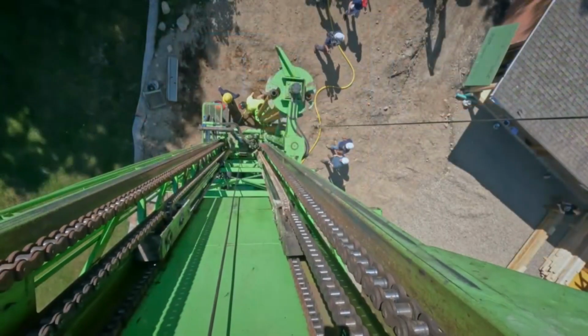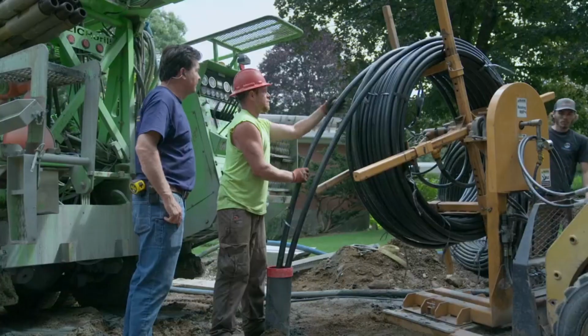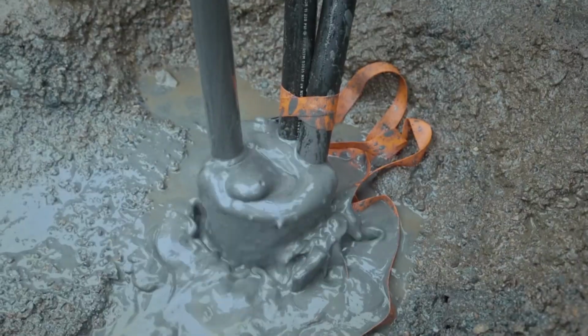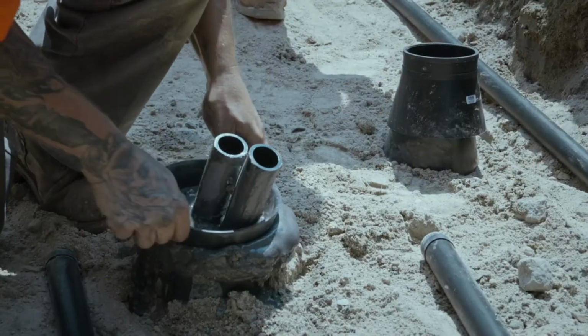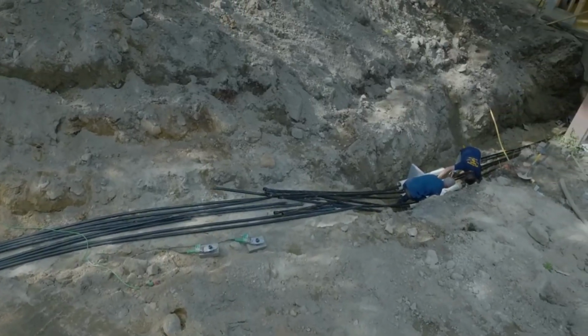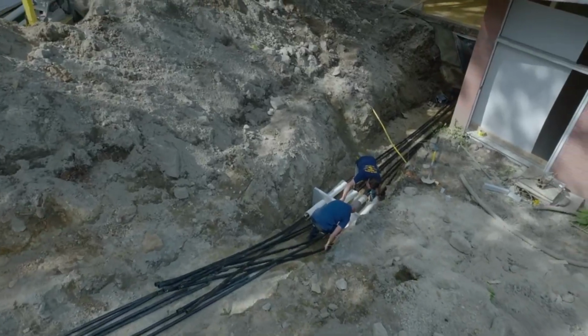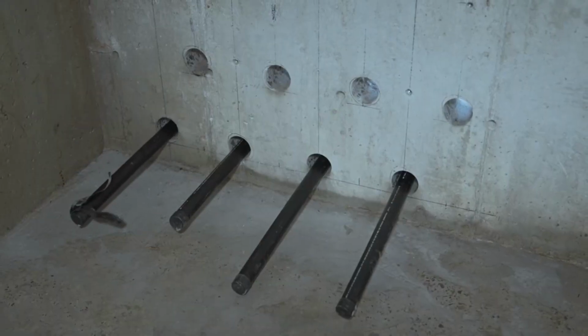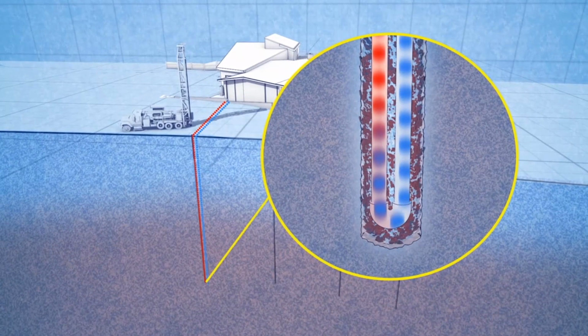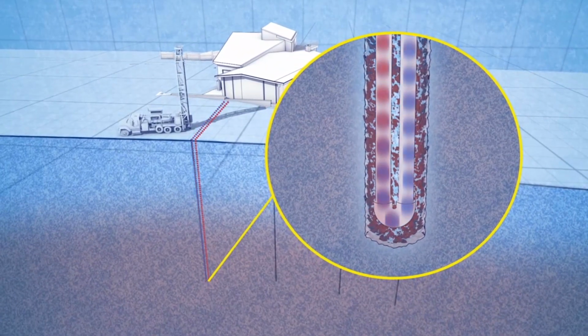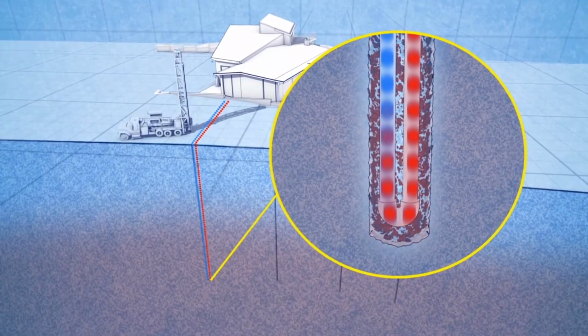Yeah, right? There are 4 holes that are drilled 500 feet deep. We lowered a U-bend pipe system in it, filled with liquid, grouted in place. Yeah. Each one of those supply and returns makes their way through trenches into the foundation wall. Right. And that is how they extract the heat and reject heat to the ground. So it can pick up some of that 50 degrees that's under the ground, transfer it into the heating inside the building, and we can heat this place for almost free. That's right. Cool.